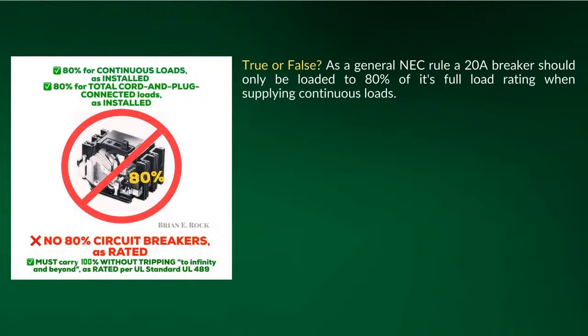So that's where the confusion comes in with this. A lot of guys, and I'm not going to name names, there's some certain code people out there that just say to do everything continuous, then you never can go wrong. But to me, that doesn't pass an exam, and that doesn't make you a knowledgeable electrician out in the field. So we like to bring the truth and show everyone that if you are all non-continuous loads, you can load all the way to 20 amps, 100% of its ampere rating.